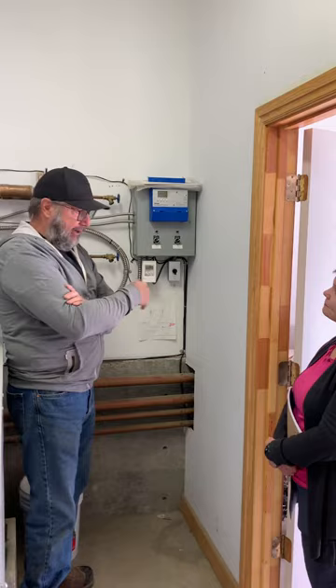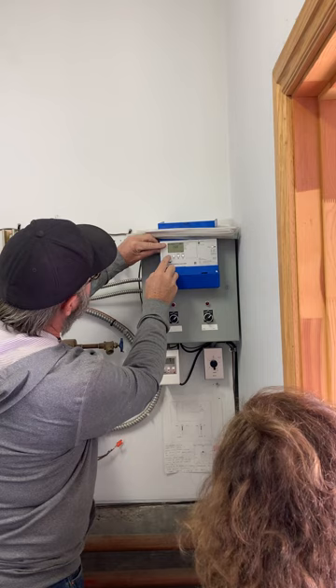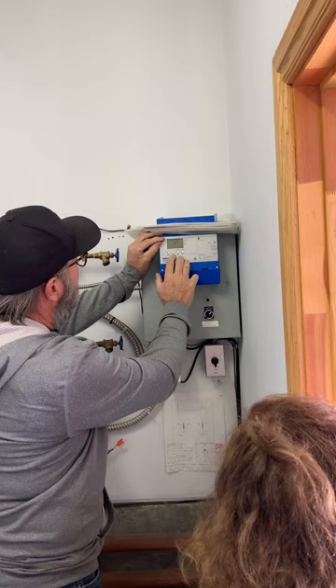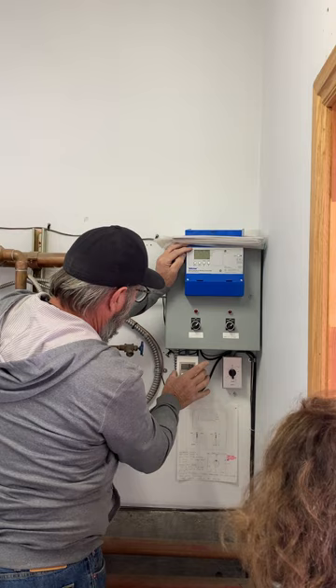So to check that, we've got a menu over here. And as I push that, I don't know if you can see on this side, it says adjust and it goes down. The two we were most concerned with is the top one. We're going to view what's in there. So let's go to an item. Outdoor right now, it's 61 degrees. That's your outdoor sensor. Probably that wire right there. And is that what it's telling me here? Oh, yep, 61. Yep, okay. Not in love with these, but let's just leave it.